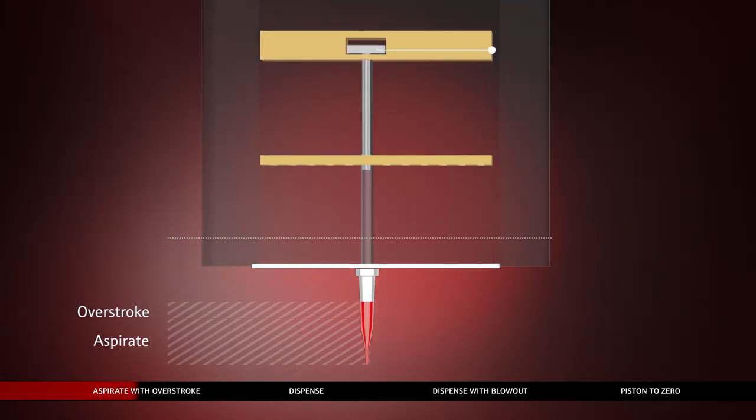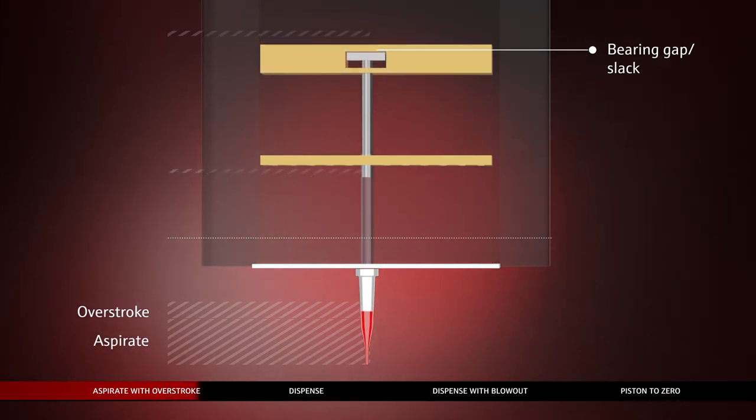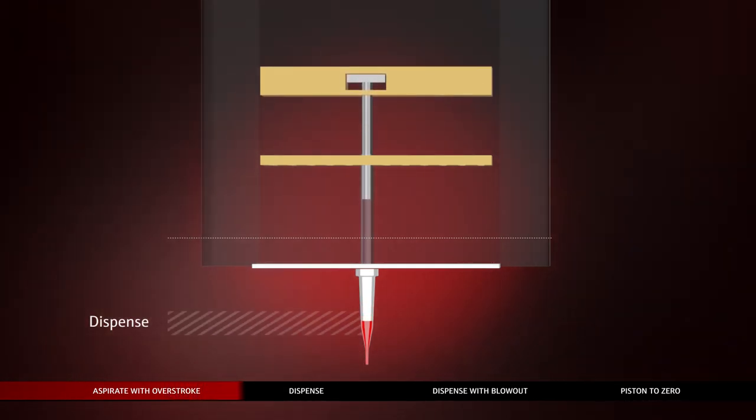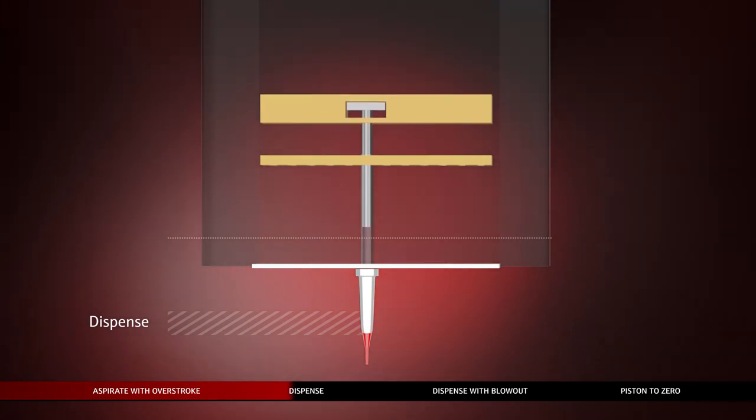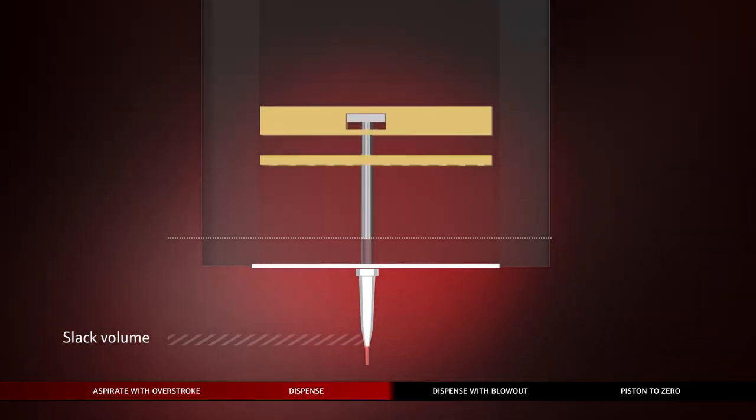The desired volume and an additional volume known as the overstroke volume are aspirated during this step. The piston moves forward, executes the piston reversal, and a slight downward movement to ensure that the exact desired volume can be dispensed into the target cavity, which is the dispense step.